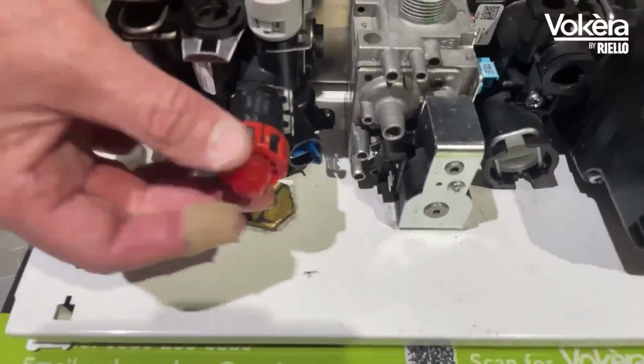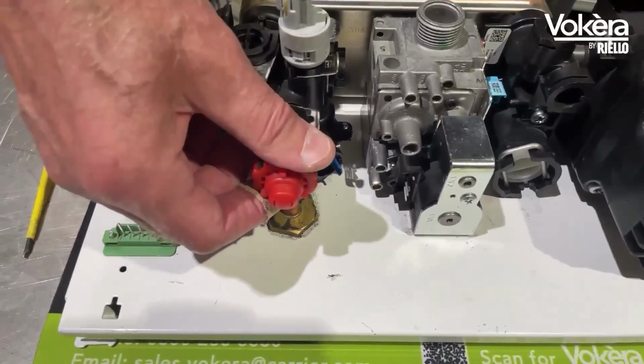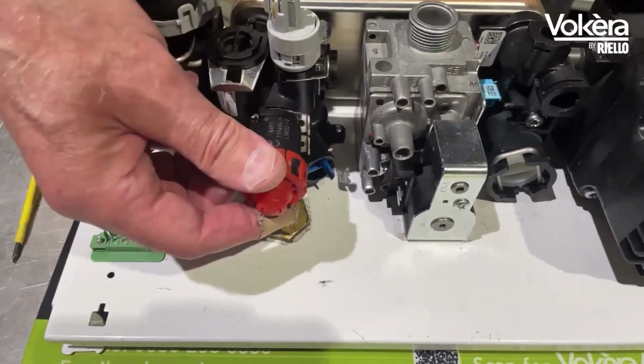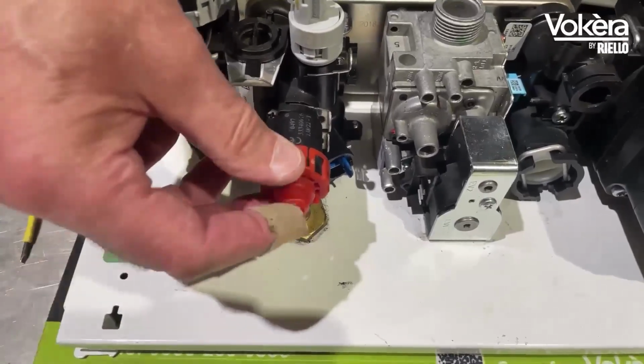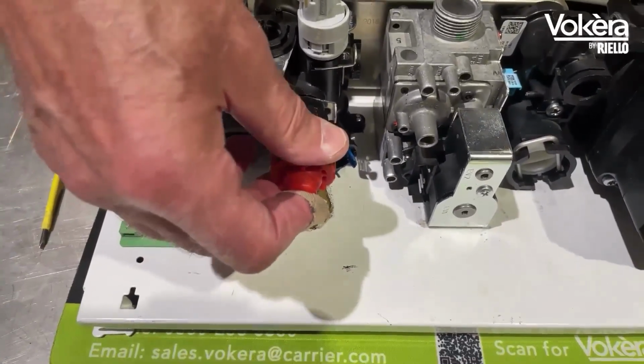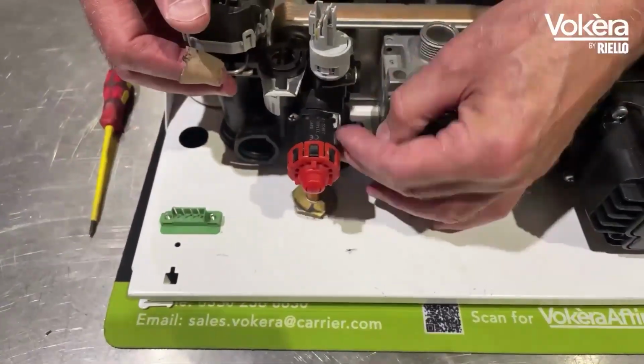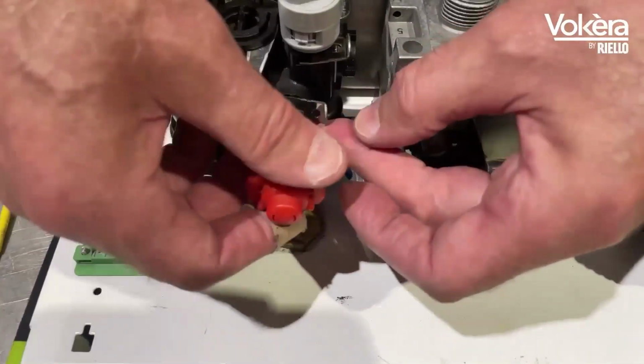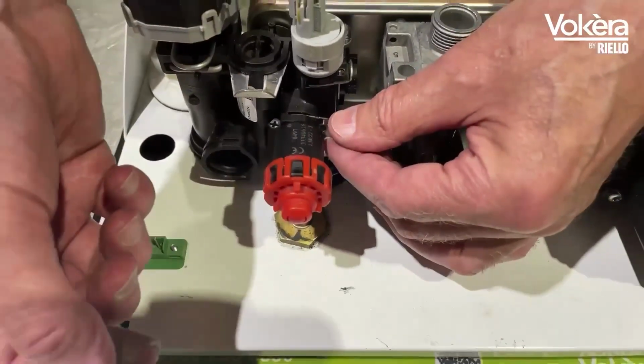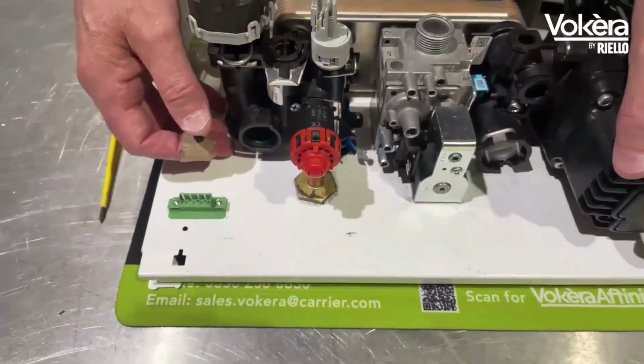We do not want you to drain the boiler through the PRV cap here. It's one that you can't adjust and drain the boiler through. But if you need to change it, remove the pin, undo the nut, pull the PRV out.